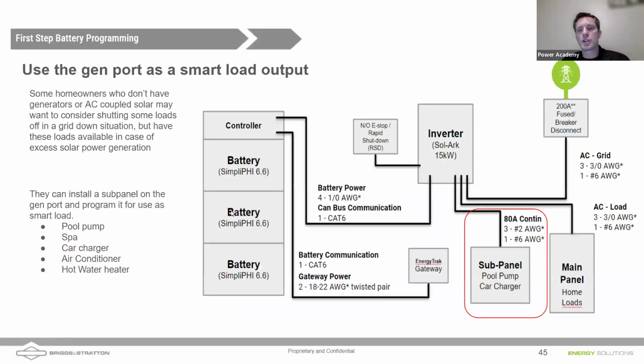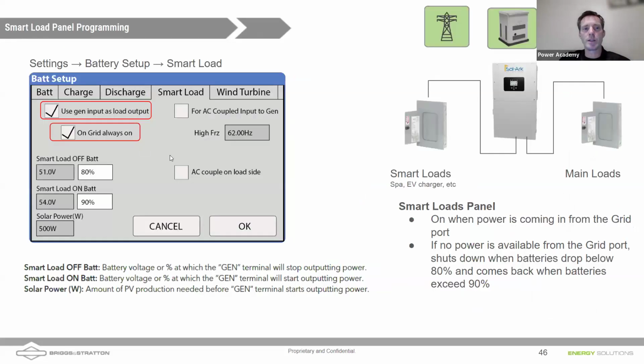If we want to use that generator port for a sub panel, we might want to use that generator port as a load output. We can do some load shedding with that based on battery percentage. So I've shown here on the screen some typical loads that you might want to get rid of in a grid down event based on battery percentage. Out of that Sol-Ark gen port, we can have a sub panel that has some loads that we're willing to shed based on battery percentage. That can be up to 80 amps of continuous 240 volt AC power, so a decent amount of power, 19 kilowatts we could put on that. And we could shed that in a grid down event based on battery percentage. I think this is one of the great features of the Sol-Ark.